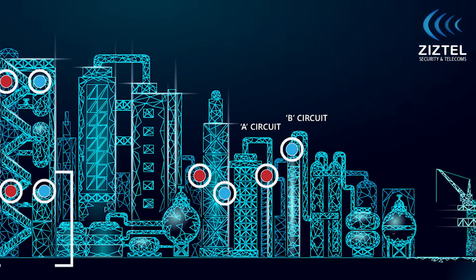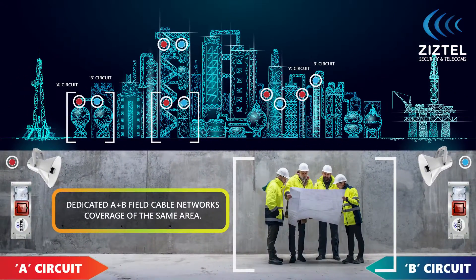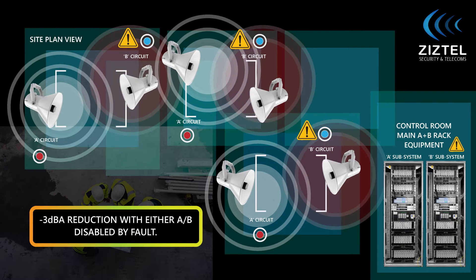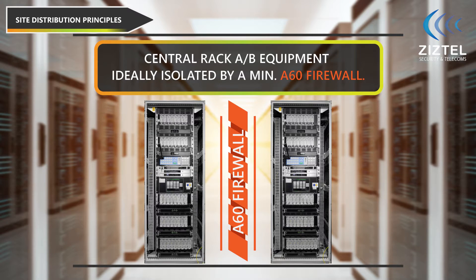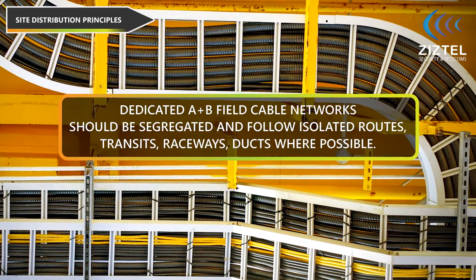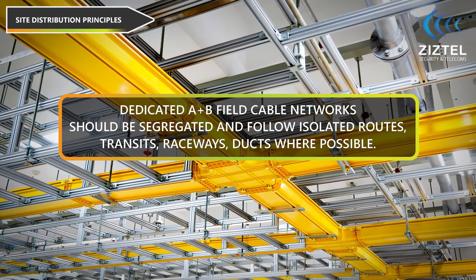This means a minus three decibel sound pressure reduction with either A/B subsystems affected by a fault condition. A/B rack equipment should ideally be separated by a minimum A60 firewall. A/B field cable networks should be segregated following isolated routes through transits, raceways and ducts where possible.